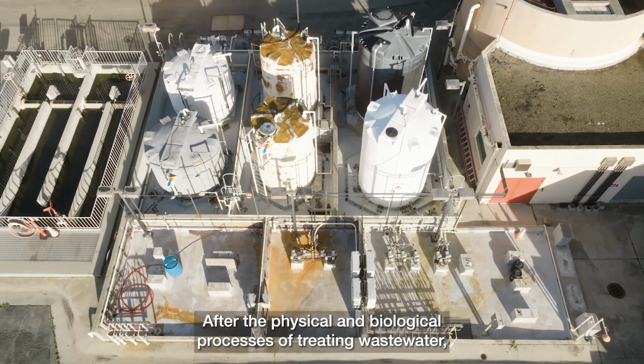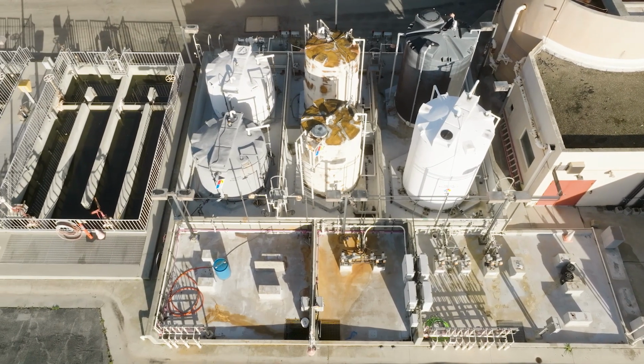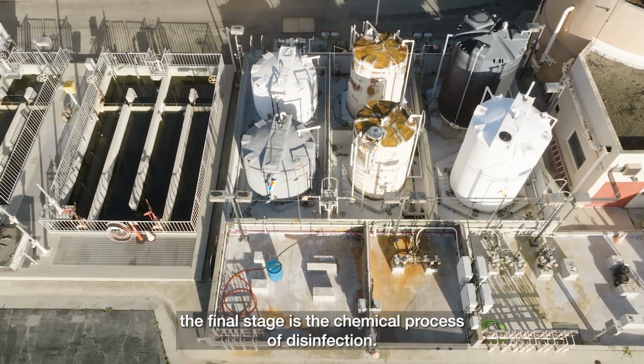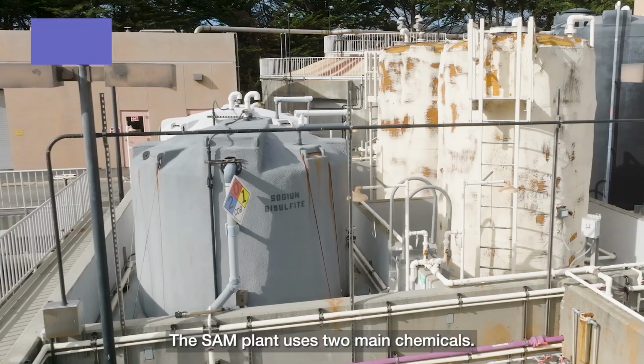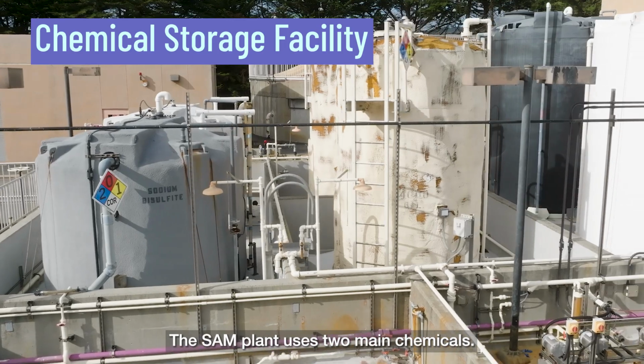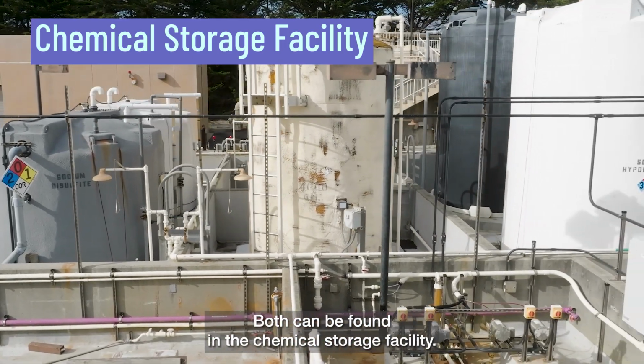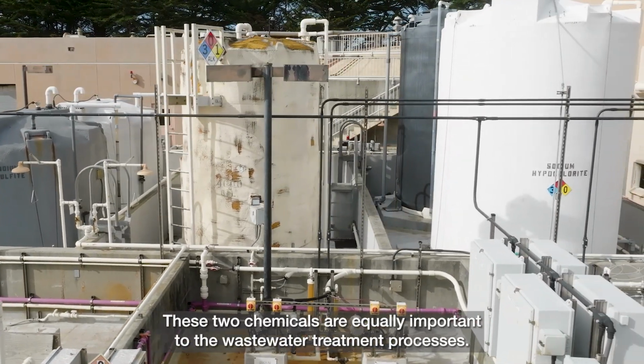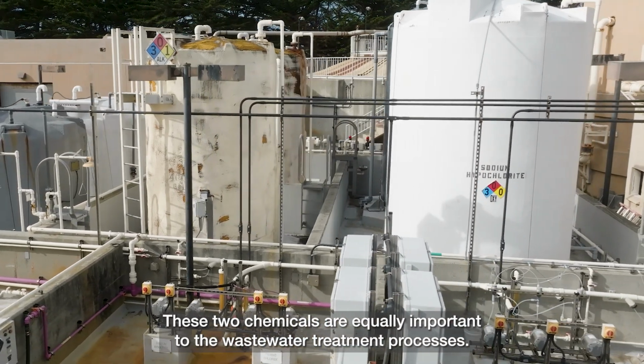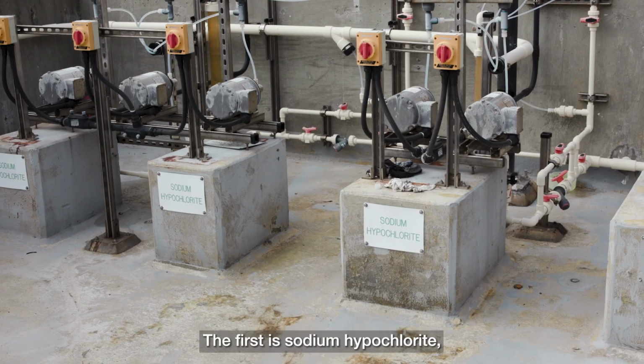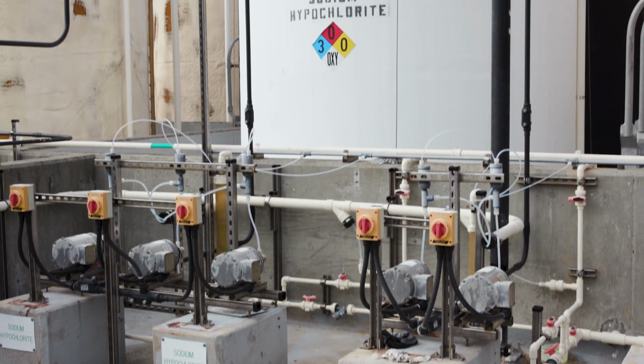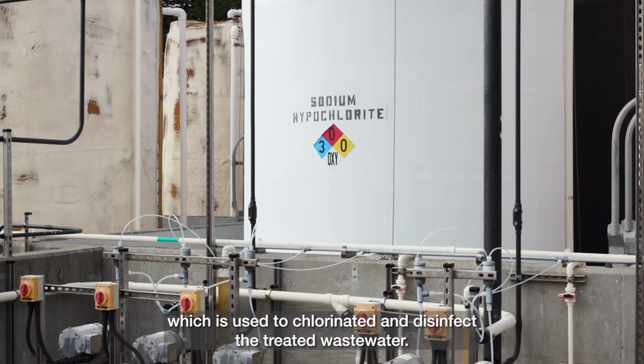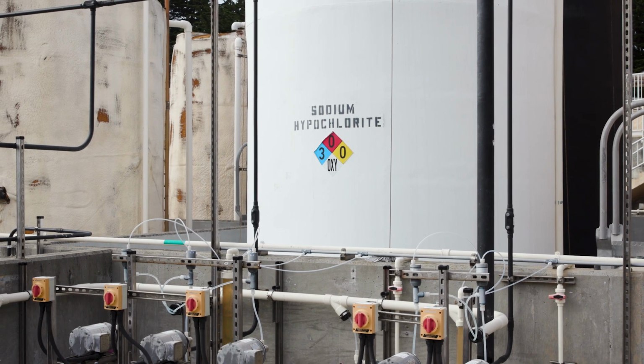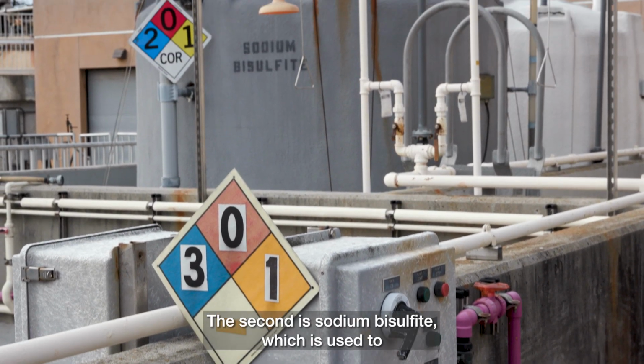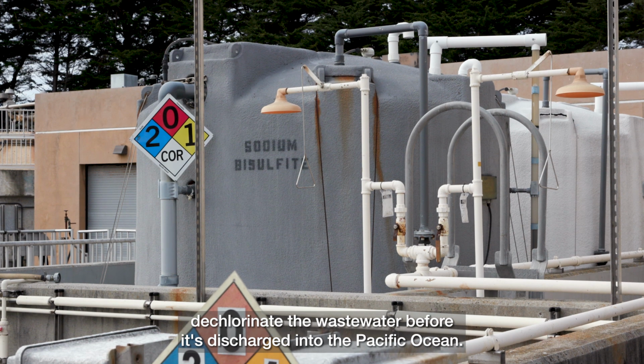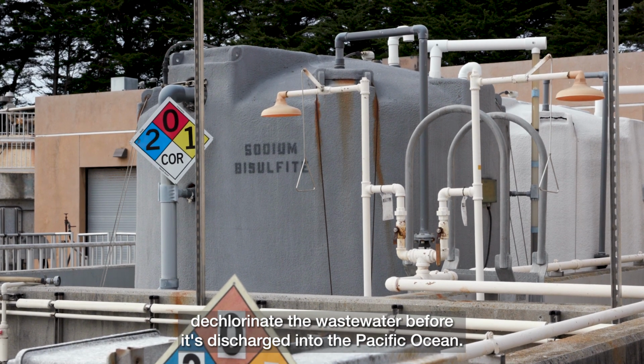After the physical and biological processes of treating wastewater, the final stage is the chemical process of disinfection. The SAM plant uses 2 main chemicals. Both can be found in the chemical storage facility. These 2 chemicals are equally important to the wastewater treatment processes. The first is sodium hypochlorite, which is used to chlorinate and disinfect the treated wastewater. The second is sodium bisulfite, which is used to dechlorinate the wastewater before it's discharged into the Pacific Ocean.